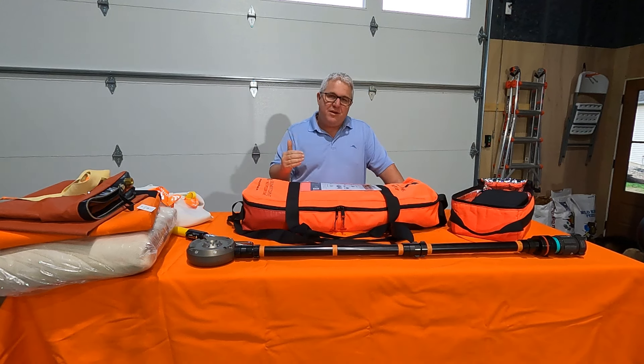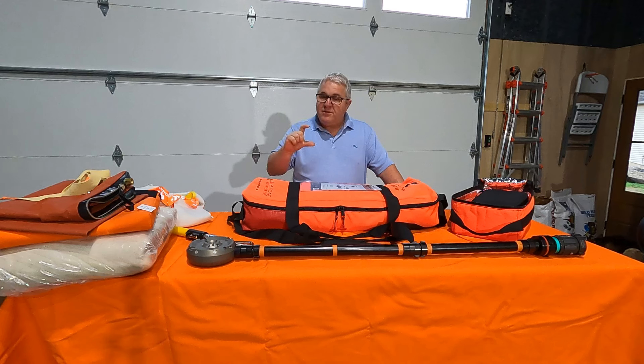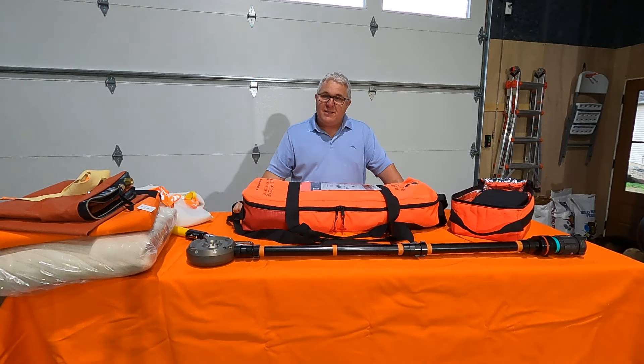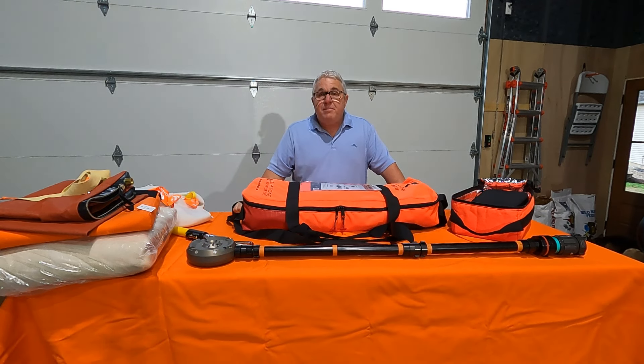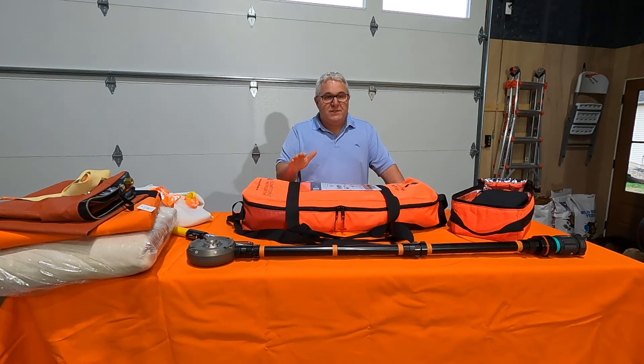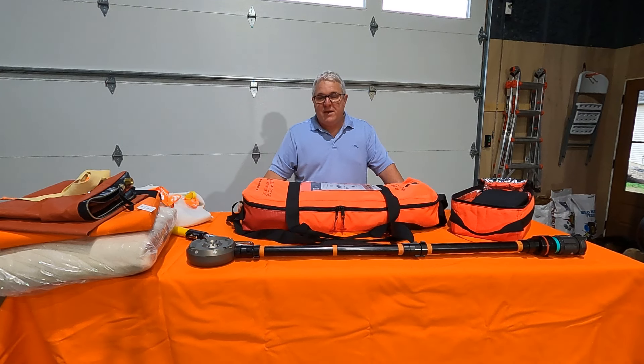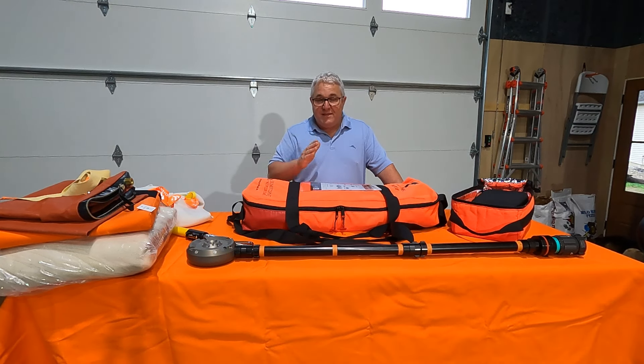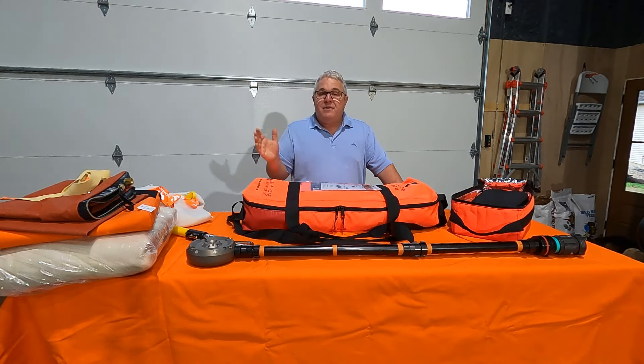Free oxygen is absolutely 100% your enemy. It's still going to potentially be an event underneath the blanket, but it won't be a wild show. You may actually have vapor cloud ignitions under the blanket, but even those — our firefighters were all very nervous to start with, we didn't know what to expect. We took every precaution, so we were safe, but we were trepidatious and rightfully so. By the end of all our testing, we had gained a lot of confidence.